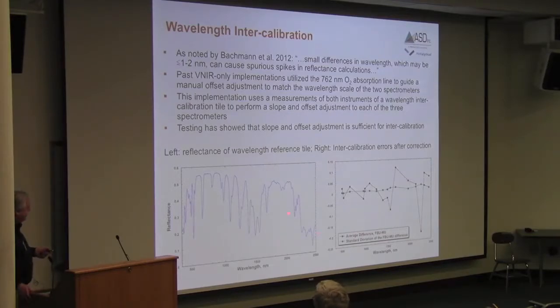We need the mylar because the mylar gives us a few sharp features out here where the rare earths don't have very many features. Now, we're not relying on this in any way for any kind of absolute calibration, really just a relative. So we view it with both instruments. One of the instruments gets designated as the master, and then we do a fit of one set of peaks on the one instrument to the other one, and then we just do a slope and offset correction to the wavelength calibration of that instrument to line the two up.